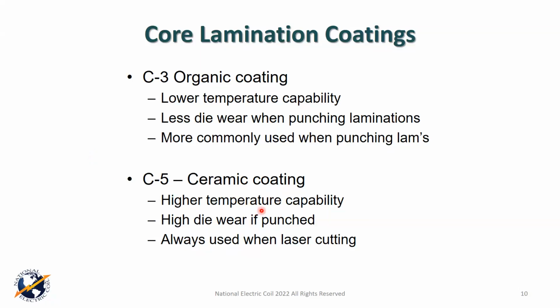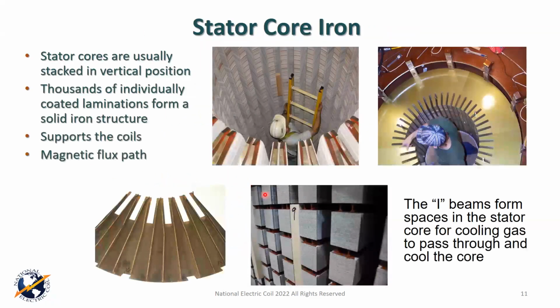The laser is very common there. Even when you're doing a minor repair or a partial restack, it's very common to go and laser cut. The ceramic does better with the laser cutting. And in some of the processes that we use when we laser cut, we usually put another coat on after it's laser cut, but the laser cutting does much better with ceramic and withstands the heat. So that's kind of the story there.